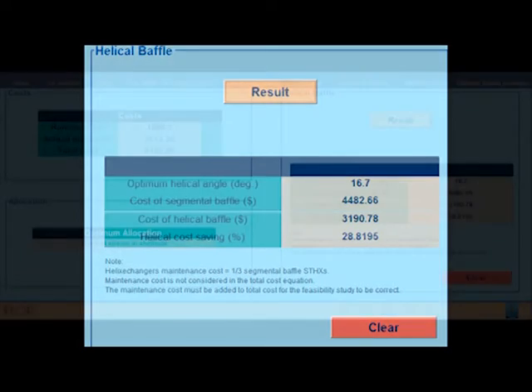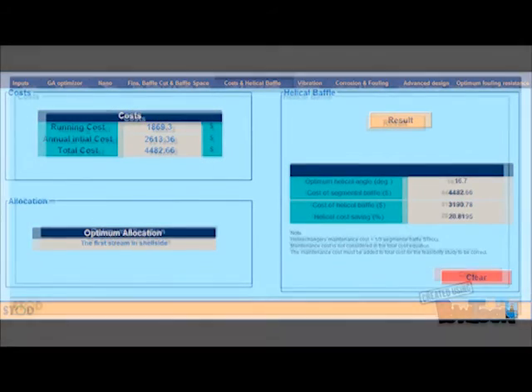Here, the designer can check the feasibility of using a helical baffle heat exchanger instead of a single segmental baffle. The output will be the annual cost of the helical baffle, the saving obtained due to using the helical baffle, as well as the optimum helix angle.